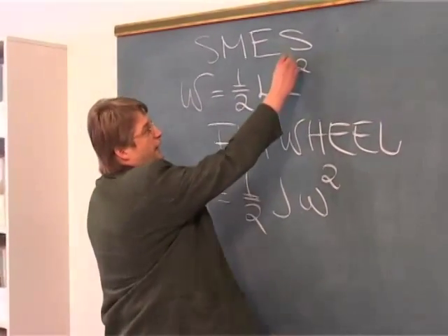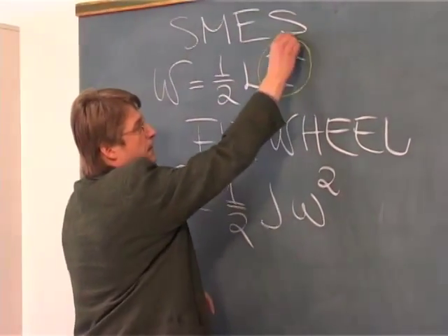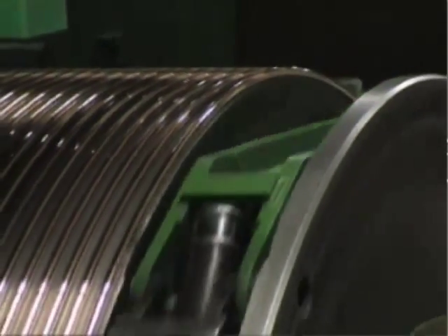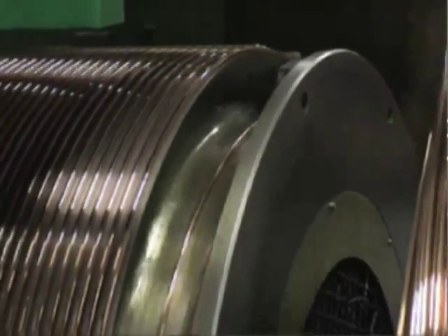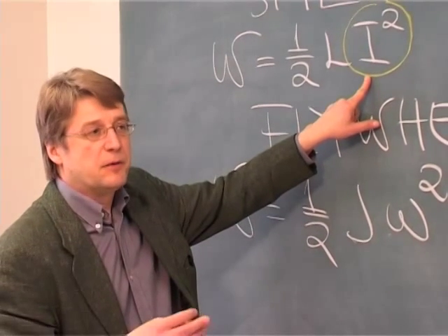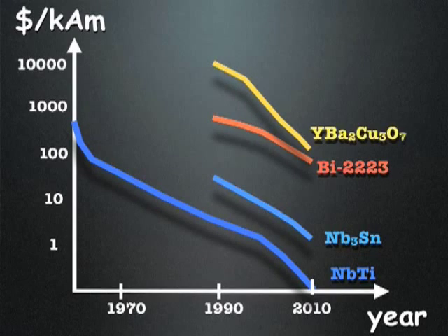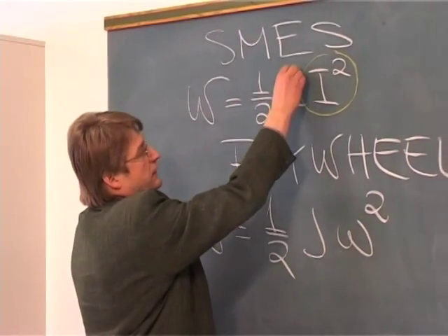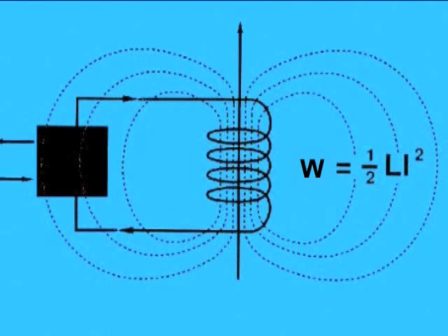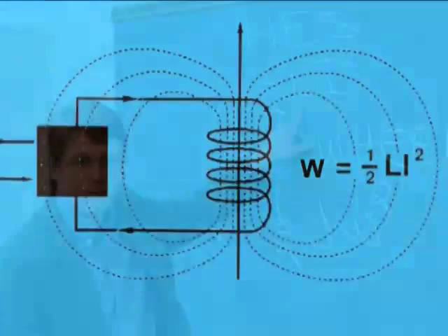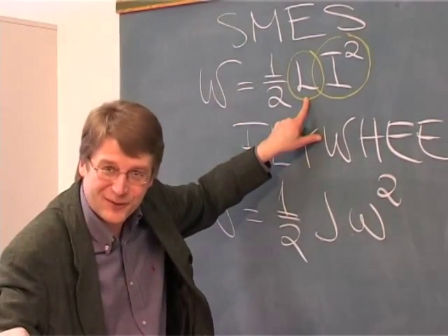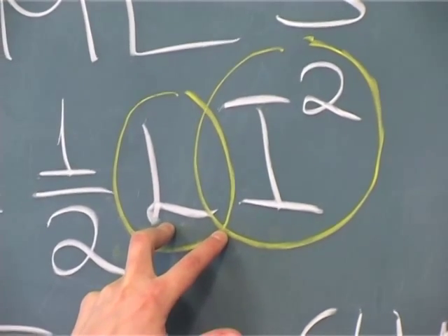If you like to increase the energy in SMES, of course we can increase the current. But if you do so, it sets quite high demands for the conductor which we use, and it may be so that the costs of the conductor will become very high. The other method is to increase the inductance. But if we do so, we must have more turns in the coil. And if we have more turns, we have more conductor, and of course it increases the costs.